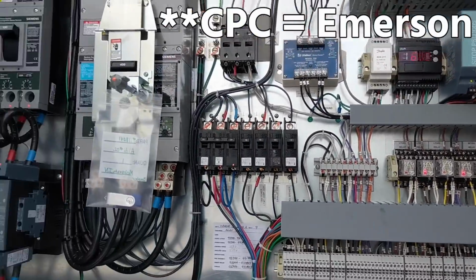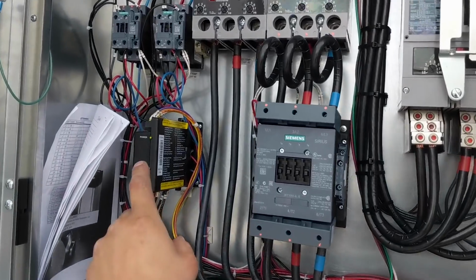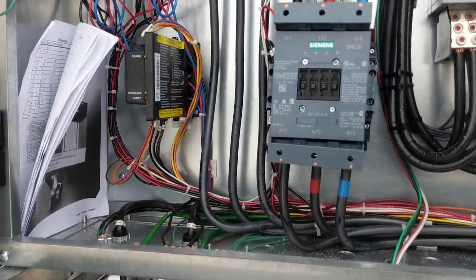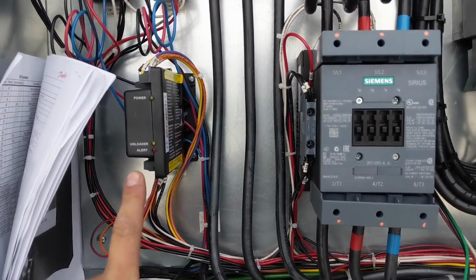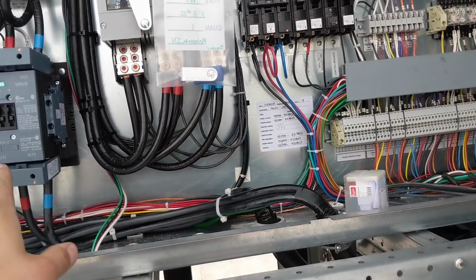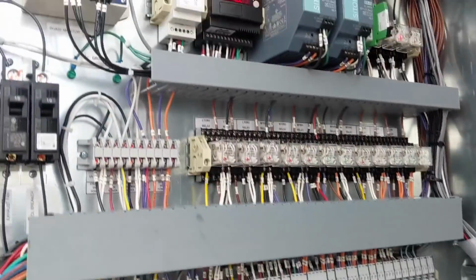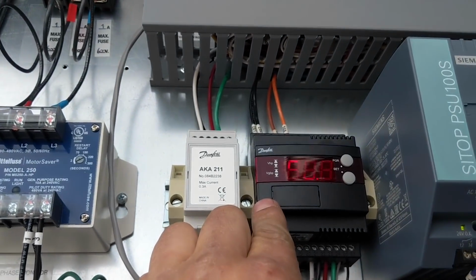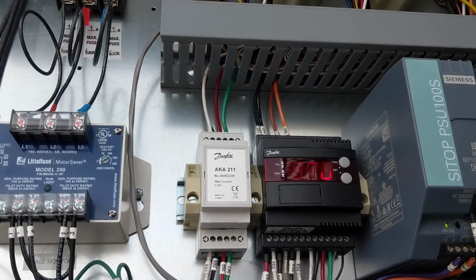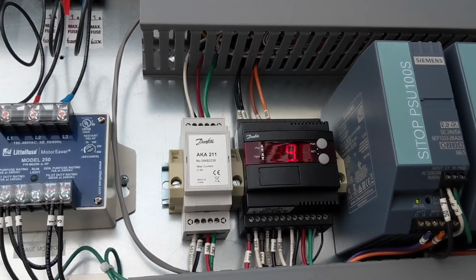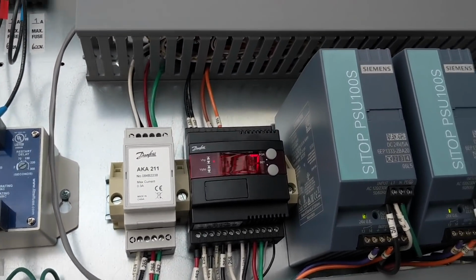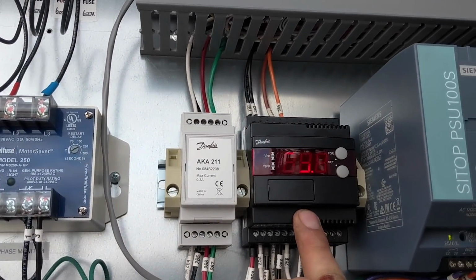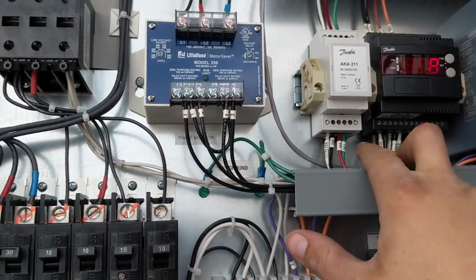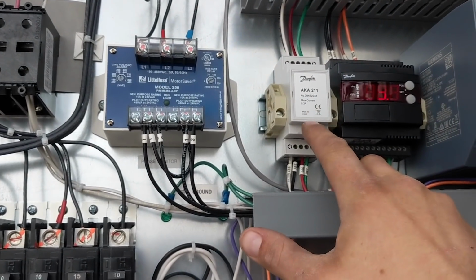So this is our main electrical panel in here. We're using CPC for our controls. We have our digital compressor controller that's using pulse width modulation to modulate the solenoid on here. We got our normal compressor, just straight up normal contactor. And over here, this is the EKC valve driver that's driving the CO2 flash tank bypass valve, and it's communicating with the high pressure valve. So it's constantly monitoring and changing the valve driver from here. This is our filter.